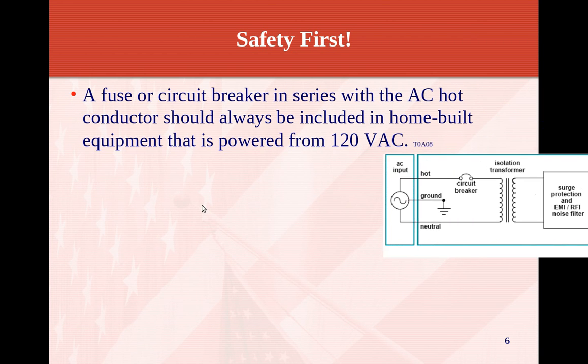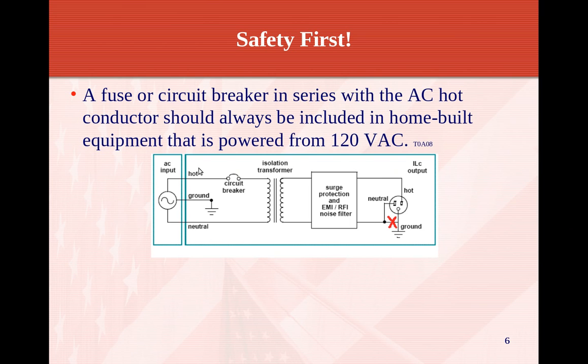A fuse or a circuit breaker in series with the AC hot conductor should always be included with home-built equipment that's powered by 120 volts. So you always need a circuit breaker or a fuse on your hot lead coming into any of your equipment if it's AC powered.